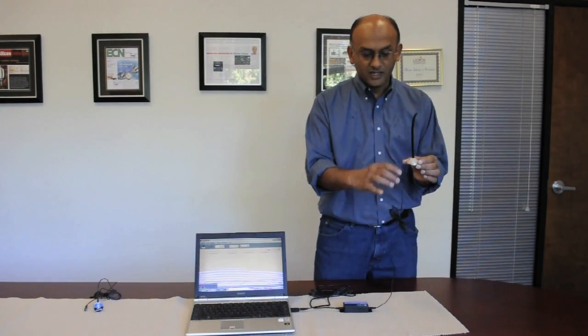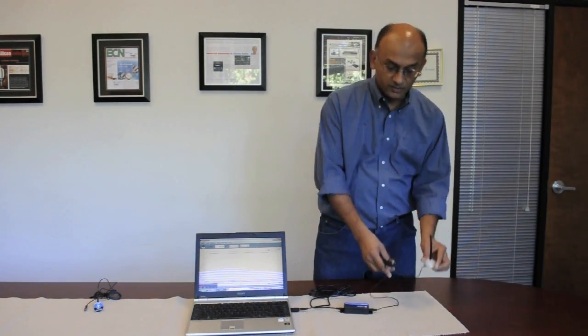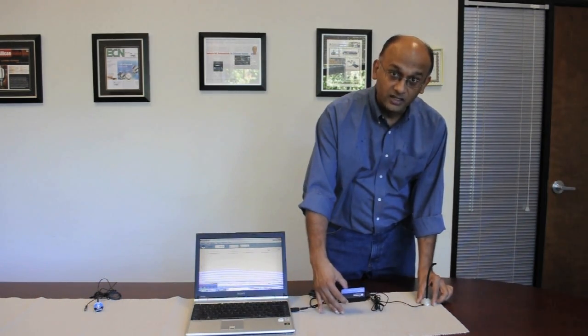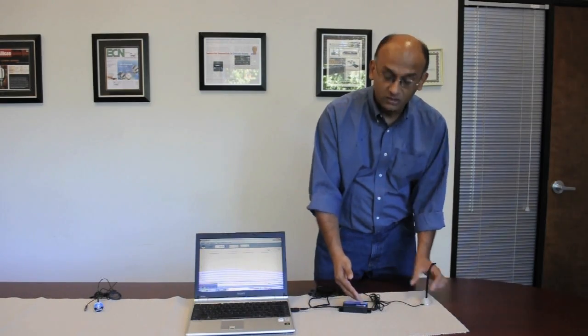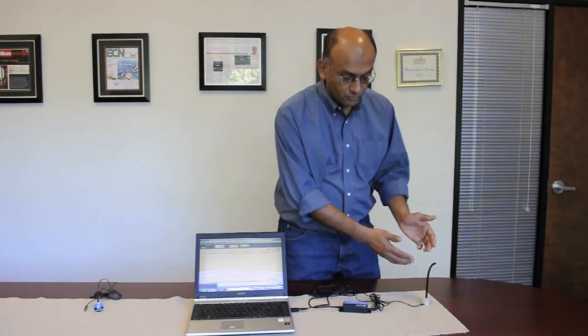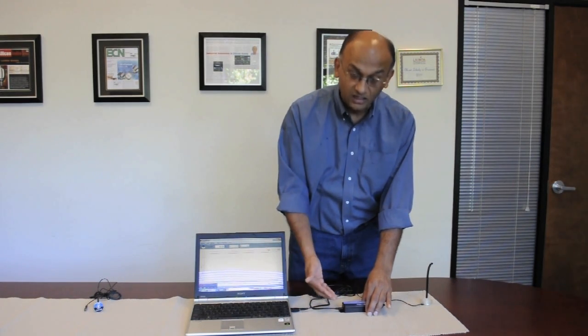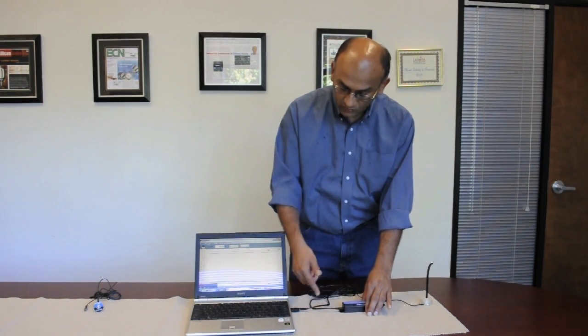This sensor, just like the Mini, has a frequency output which is proportional to the applied pressure. And then using our DQ1000 interface, it takes the frequency input, calibrates the pressure and applies a digitizing formula and converts it to a digital protocol, in this case going into a USB port of a PC.